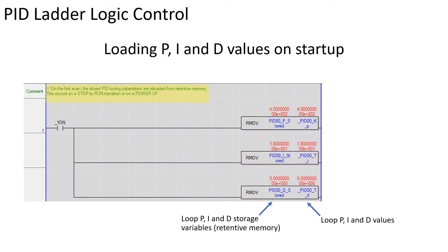On a stop to run transition or power cycle, the first scan bit enables the stored PID values to be loaded into the operational loop variables.